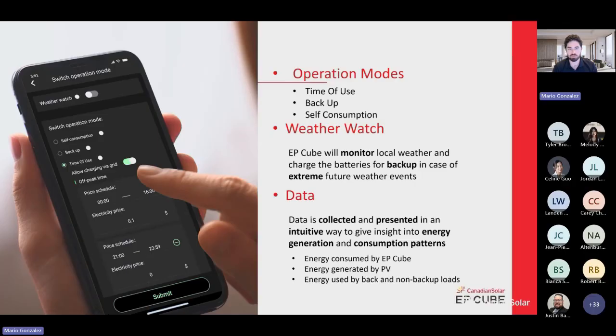And self-consumption is the most popular, in my opinion. Basically, you use the battery the most and the energy grid the least. The system is going to charge the battery only from solar, not from the grid, unless you have a minimum SOC set up for it. It's always going to keep the battery up at that SOC and pull from the grid if needed.